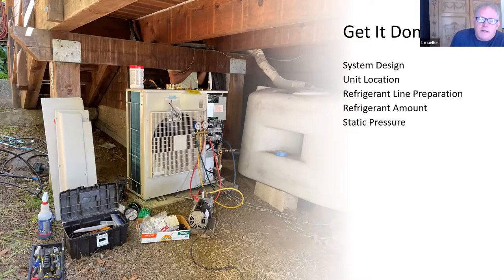It's critical. Again, this is one where for years and years, I've seen HVAC subcontractors just release the refrigerant into the system without ever removing the atmosphere from the lines, or even making any more effort than just putting the refrigerant in. But it's really critical that you get a clean, dry, evacuated refrigerant line on the system for it to be as efficient as possible.